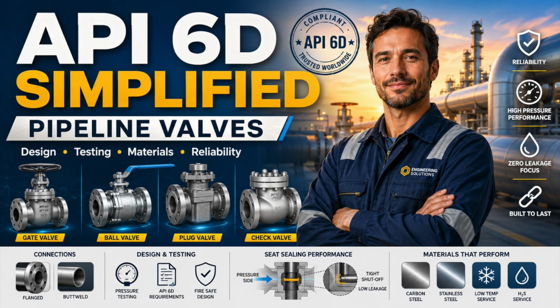Cavity pressure remains one of the most dangerous hidden failure modes. A closed valve traps liquid, temperature rises, the liquid expands, pressure increases, and seats, seals, or body joints may become overloaded. The solution is not simply to add relief. You must know where the pressure relieves and whether that relief path compromises the isolation function. Every critical isolation valve should have a clearly understood cavity pressure philosophy.